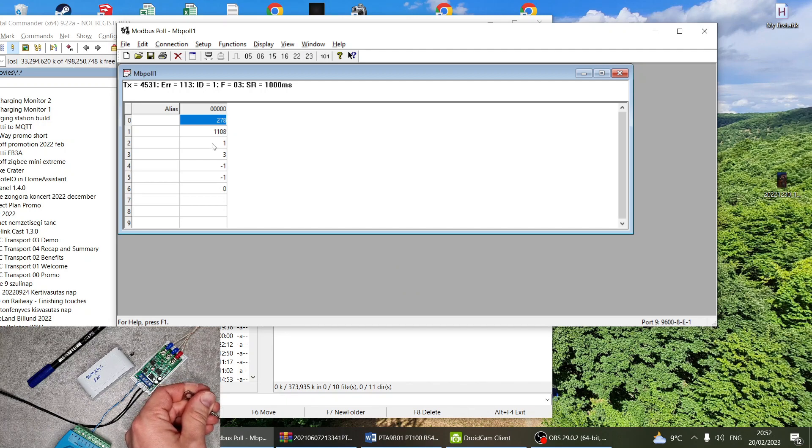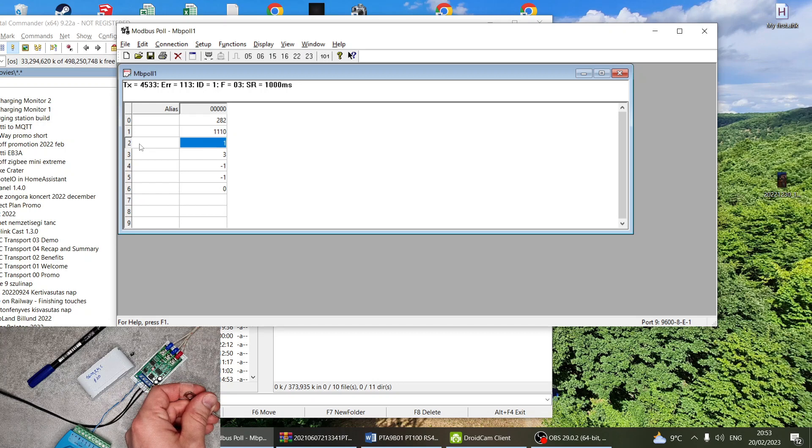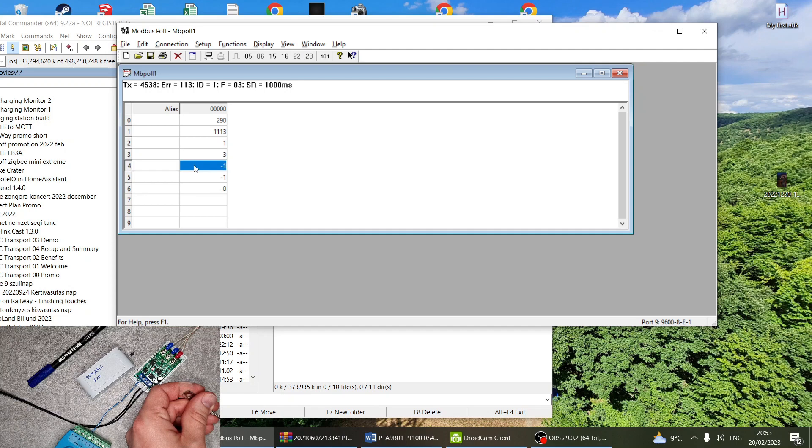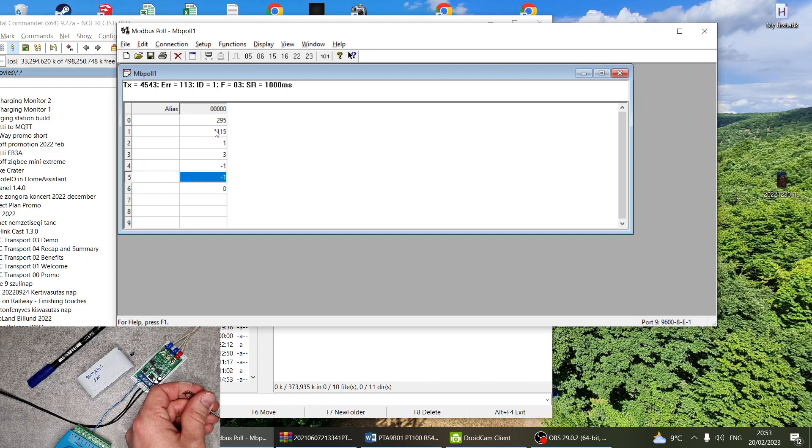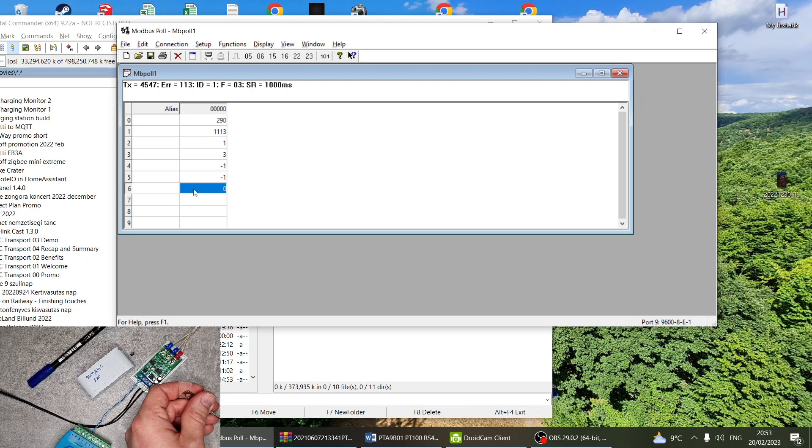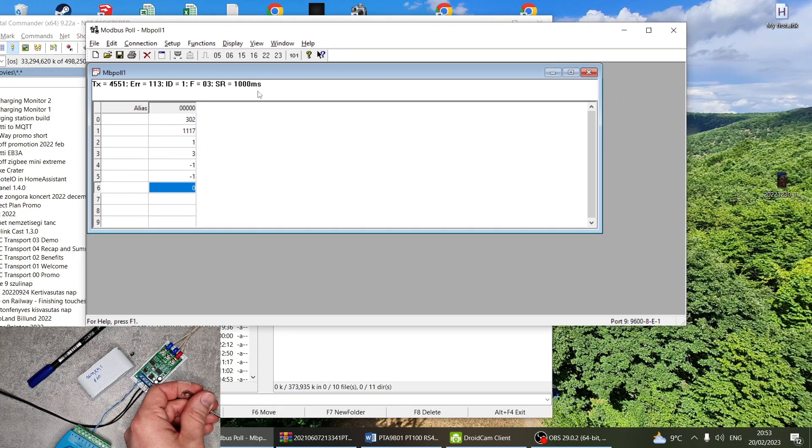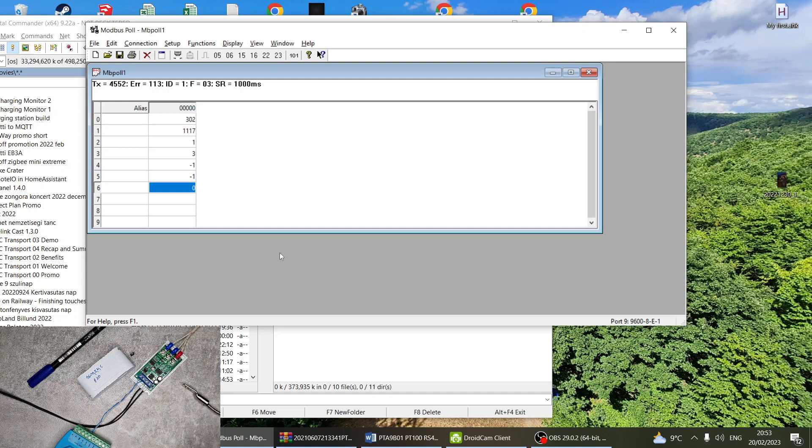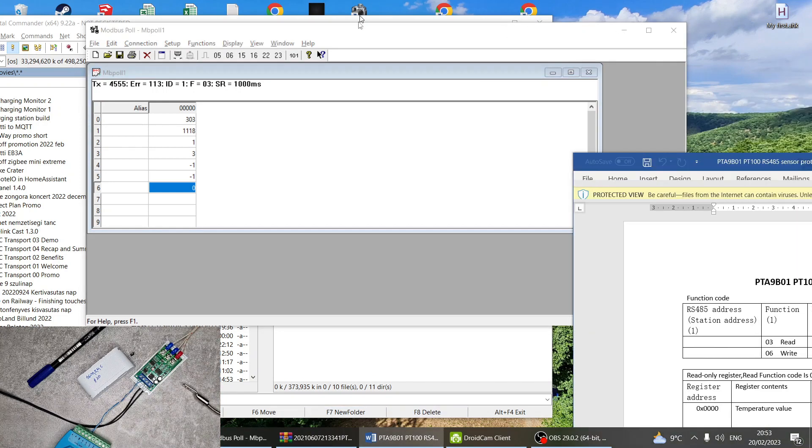Then you have on address 2 the slave ID, on address 3 the communication settings, and you have address 4 and 5 for temperature and resistance compensation. In address 6 you can set up different modes. I'm going to open the documentation for that, so it's really easy to use.